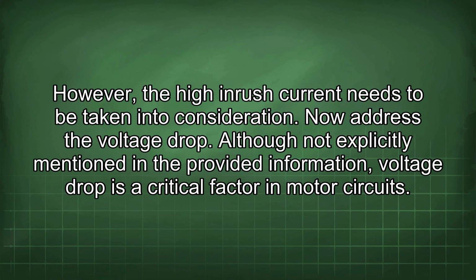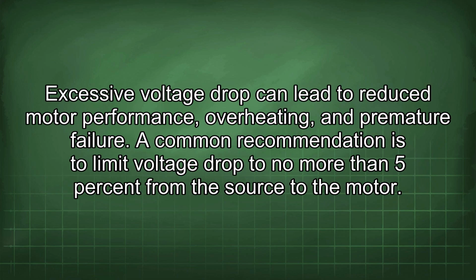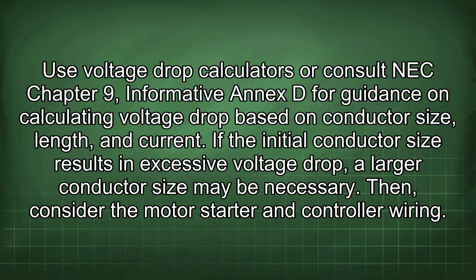Now address the voltage drop. Although not explicitly mentioned in the provided information, voltage drop is a critical factor in motor circuits. Excessive voltage drop can lead to reduced motor performance, overheating, and premature failure. A common recommendation is to limit voltage drop to no more than 5% from the source to the motor. Use voltage drop calculators or consult NEC Chapter 9 Informative Annex D for guidance on calculating voltage drop based on conductor size, length, and current. If the initial conductor size results in excessive voltage drop, a larger conductor size may be necessary.